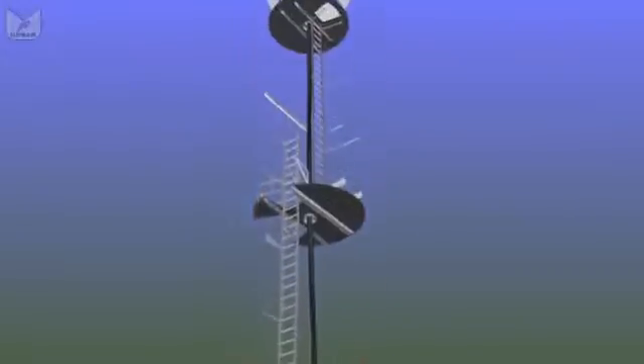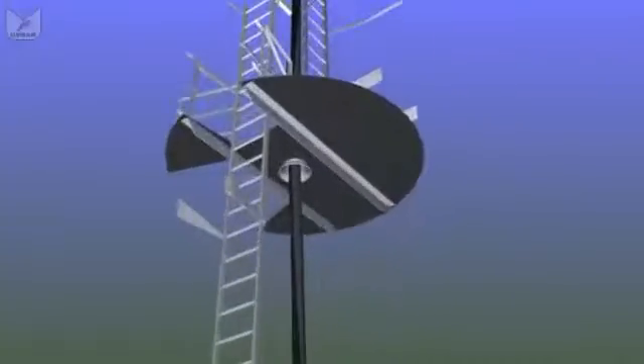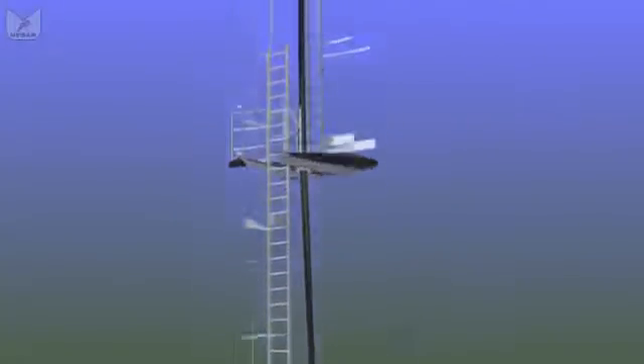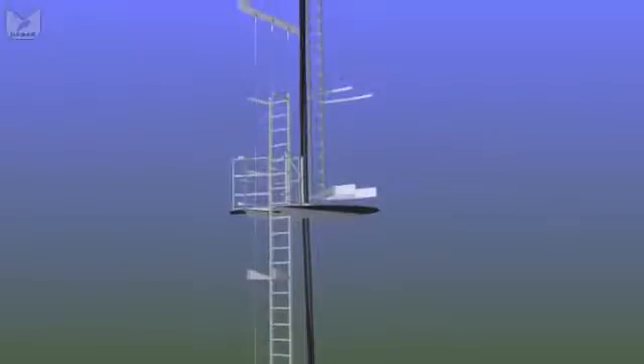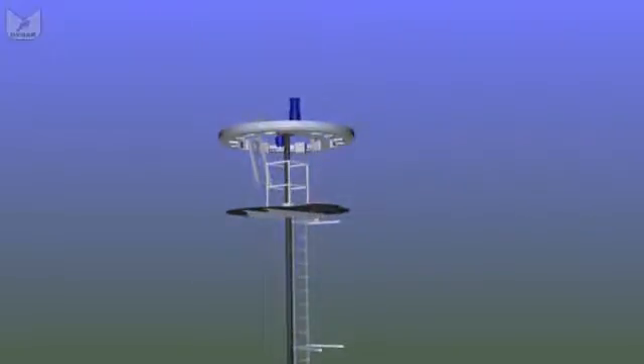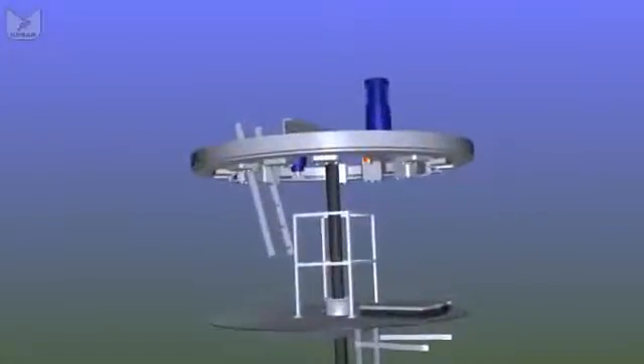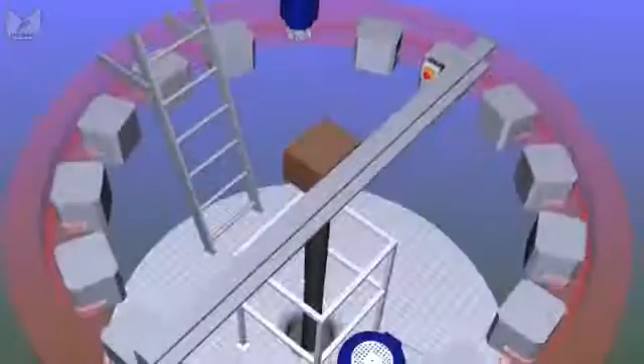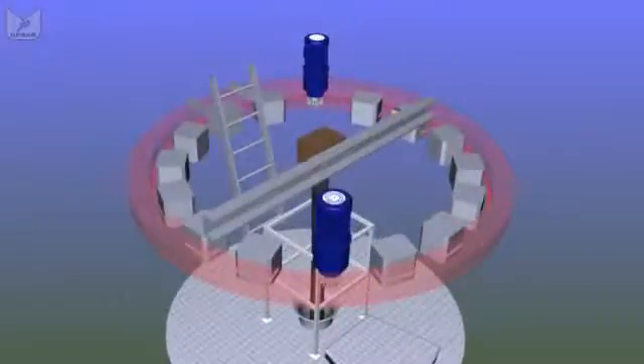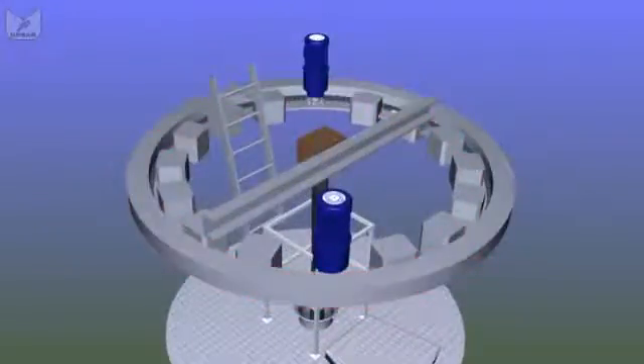The cable again breaks free from its mounting and hangs in the center of the tower for the last 10 to 20 meters or so, so that it can rotate as the nacelle yaws into the wind. The lift eventually runs out of space - remember the tower is narrower as we get to the top - so the lift tends to park itself about half a platform from the top and we have a normal ladder which then leads to the yaw platform. We have a yaw ring bolted to the underside of the nacelle joining it to the top of the tower. A series of disc brakes run around that yaw ring to lock it in position when the wind isn't changing direction. When it is, we have a series of either electric or hydraulic motors that rotate the entire mechanism around on the top of the tower.